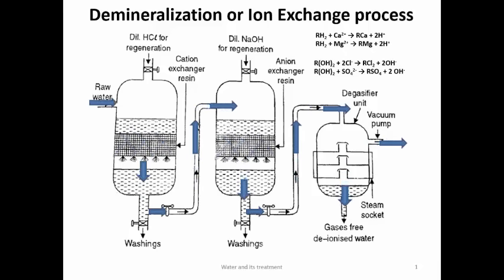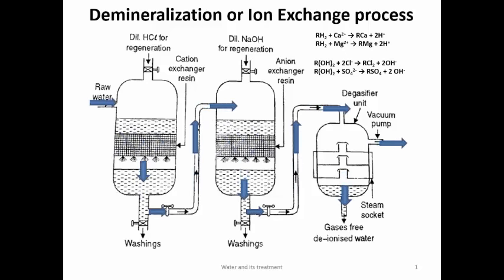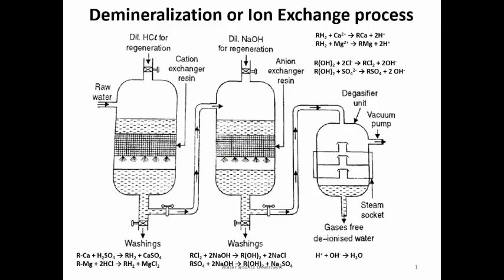After some time the resins get exhausted — all H⁺ and OH⁻ ions are replaced by Cl⁻, Ca²⁺, Mg²⁺ etc. For regeneration: dilute HCl and dilute NaOH are added from the top. For the cation exchange resin, Ca²⁺ and Mg²⁺ are replaced back by H⁺ from the acid, regenerating RH₂. For the anion exchange resin, Cl⁻ and SO₄²⁻ are replaced by OH⁻, regenerating ROH₂. Both resins are then ready to demineralize water again.